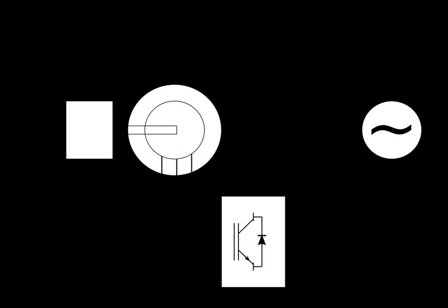The other winding, traditionally called the field, but here both windings can be outputs, is connected to three-phase AC power at variable frequency. This input power is adjusted in frequency and phase to compensate for changes in speed of the turbine. Adjusting the frequency and phase requires an AC to DC to AC converter. This is usually constructed from very large IGBT semiconductors. The converter is bidirectional, and can pass power in either direction. Power can flow from this winding as well as from the output winding.